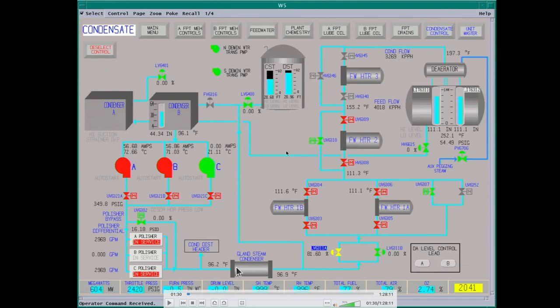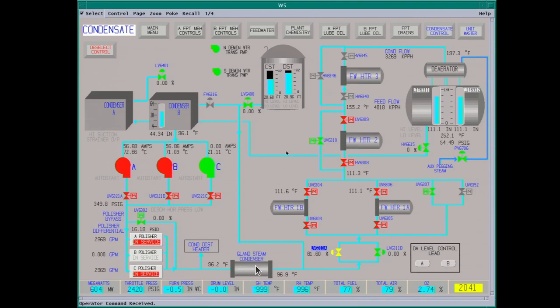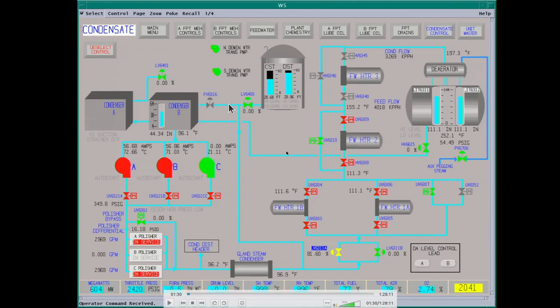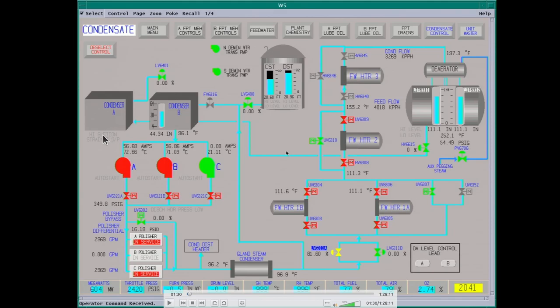From there it goes to the gland steam condenser — this handles any excess steam from the turbine sealing. From here it goes to your deaerator level control valves, then to feed water heaters 1A, 1B, and 2, which are inside the surface condenser. Feed water heater 3 is on the third floor. The deaerator is on the ninth floor, and these heaters are down on the first floor.